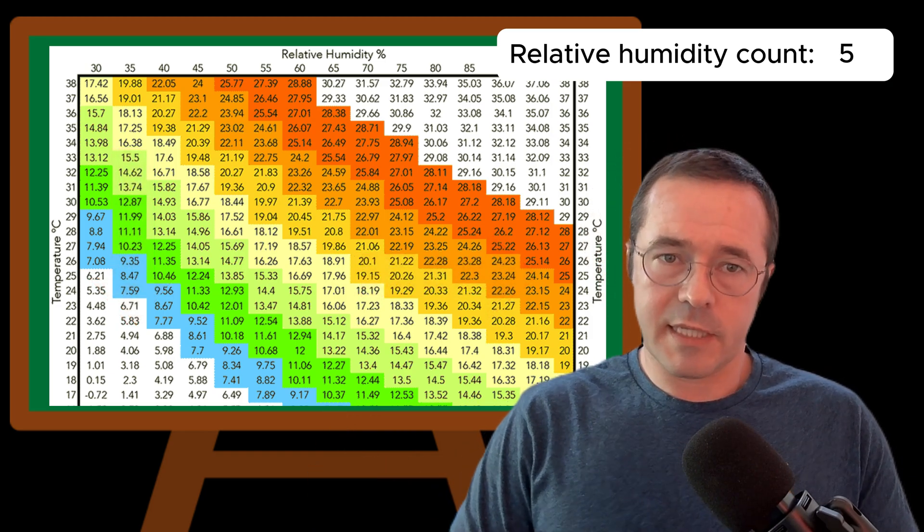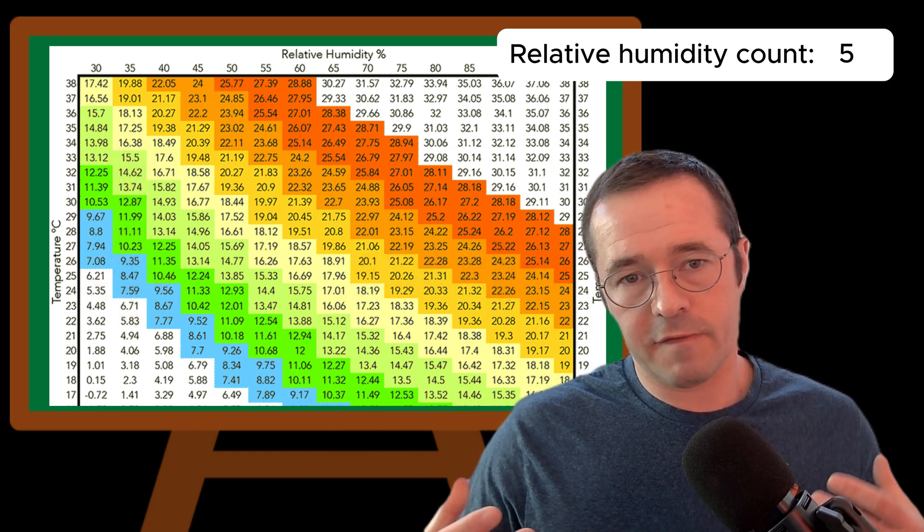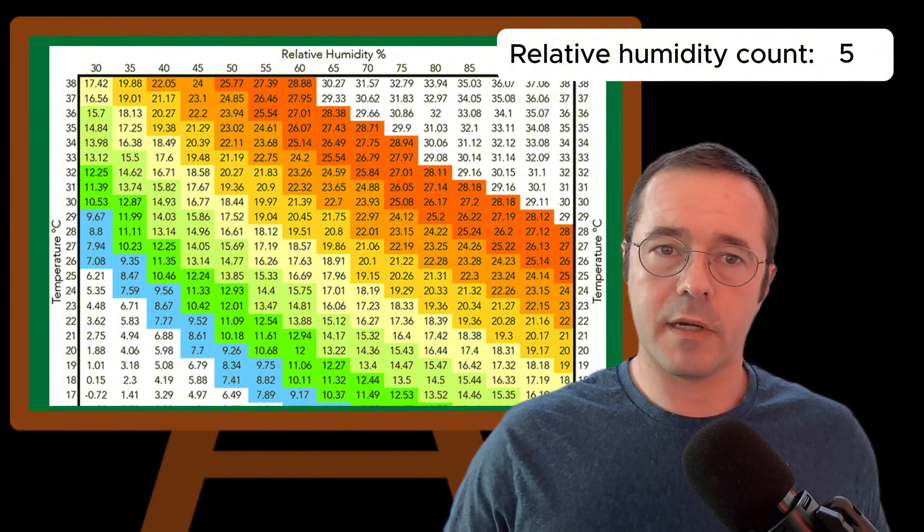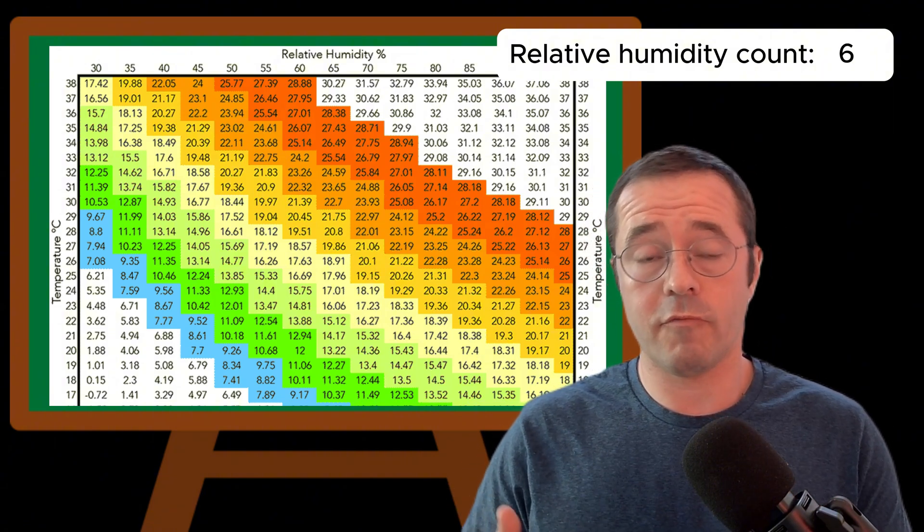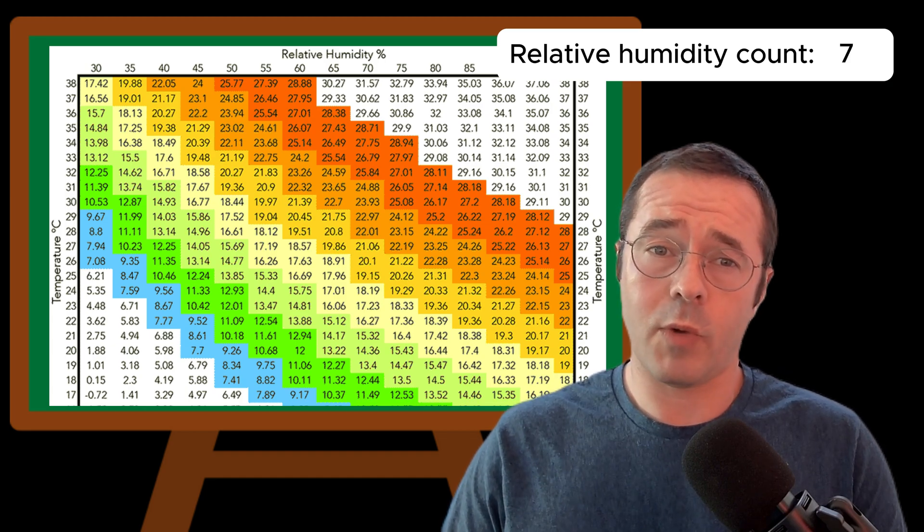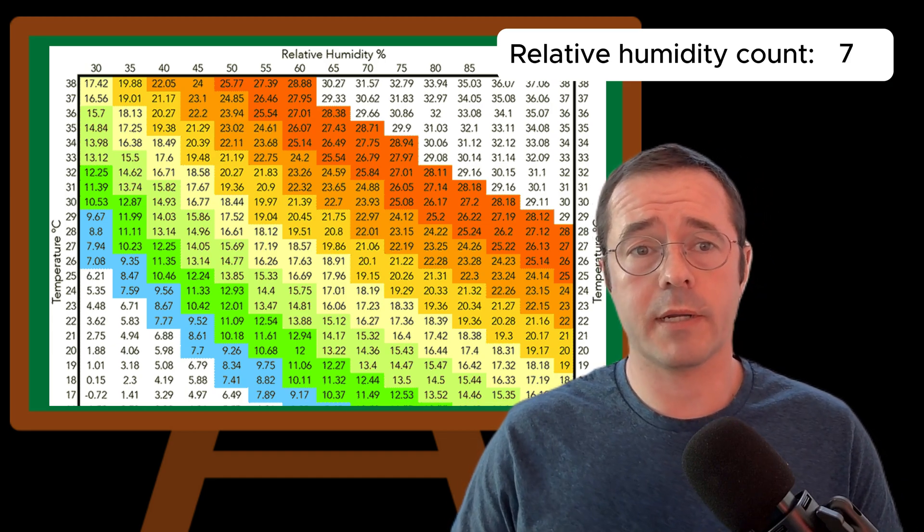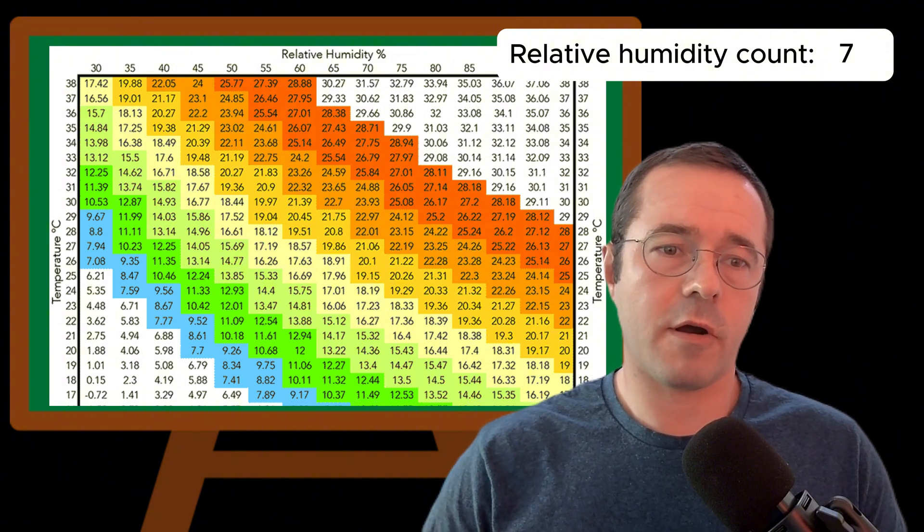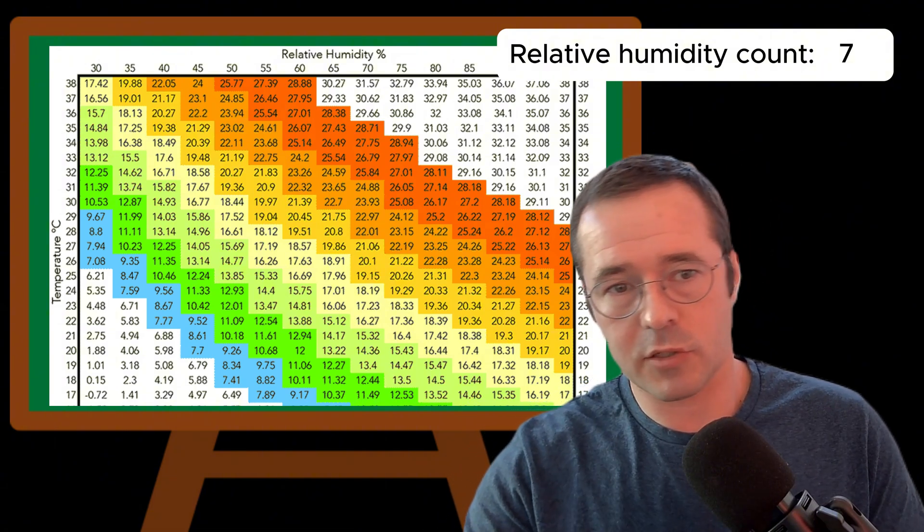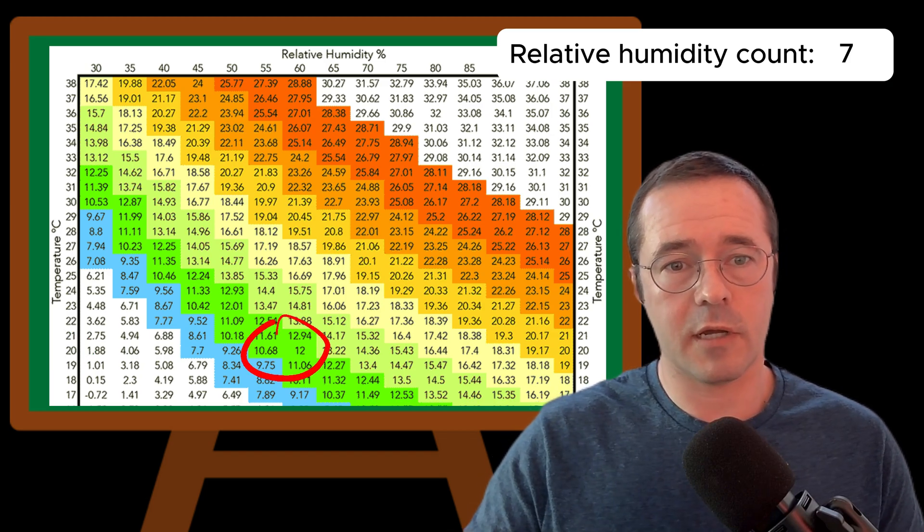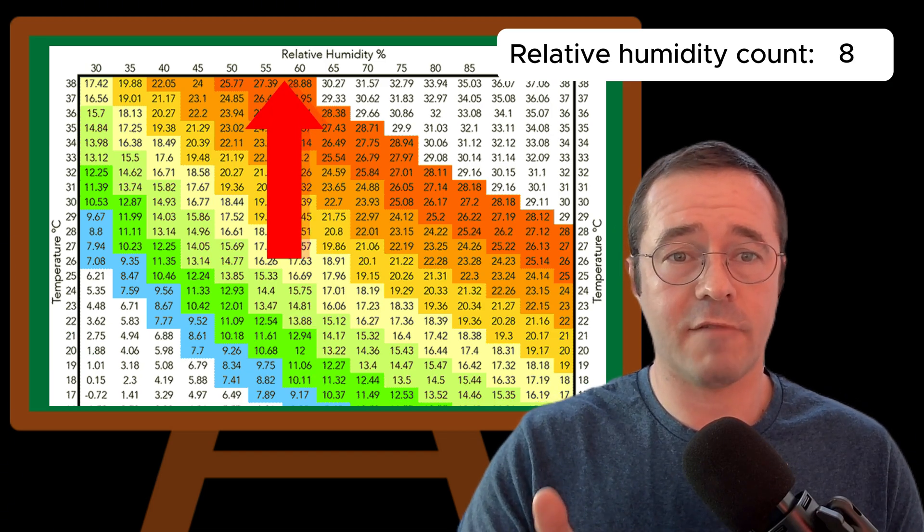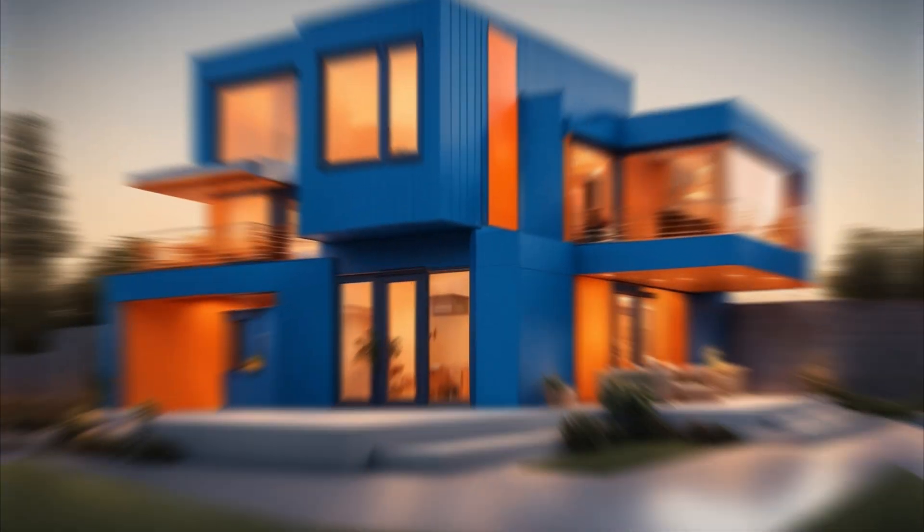And the reason that this is important is because things like comfort are judged by relative humidity and the relative humidity is also when you can gauge how mold is going to start growing as well. So you can see on this graph that if we go to sort of 20 degrees Celsius and you track across, comfortable relative humidity is going to be around 55-60%.